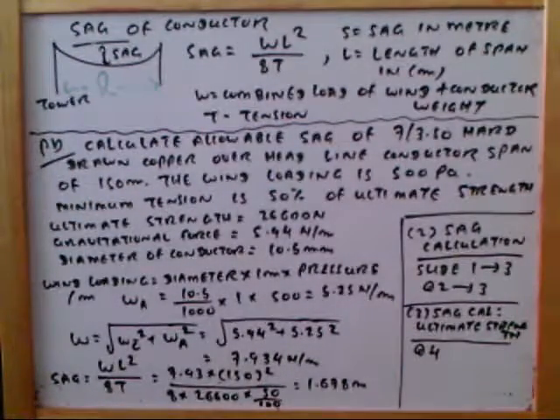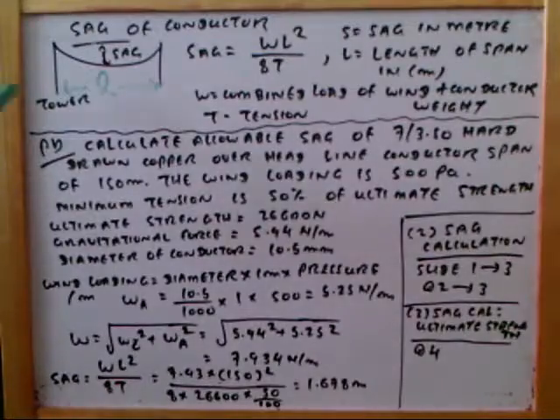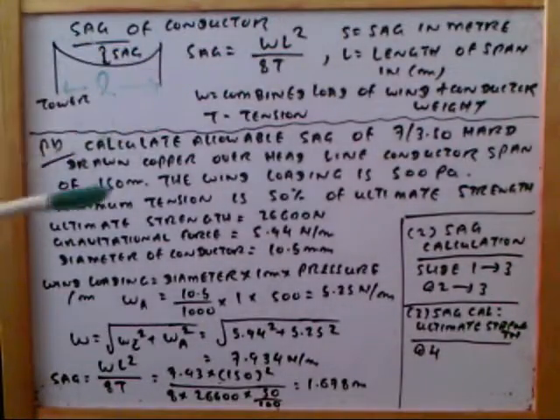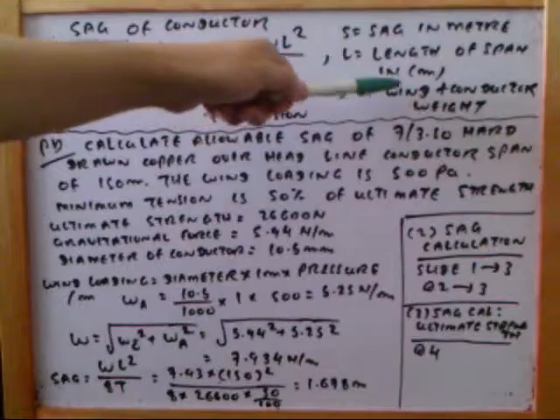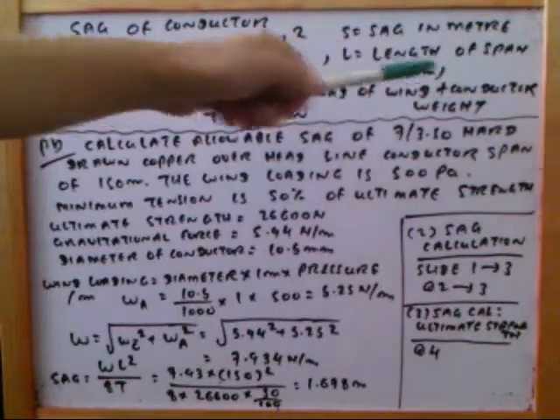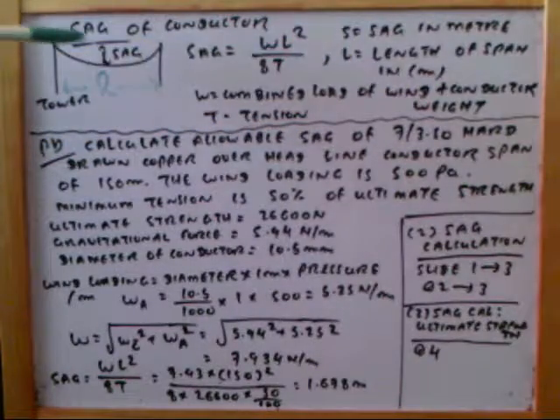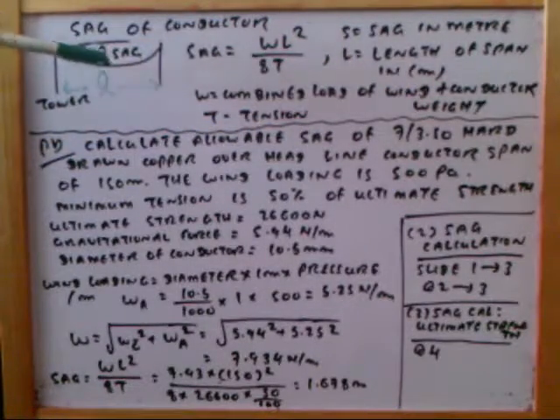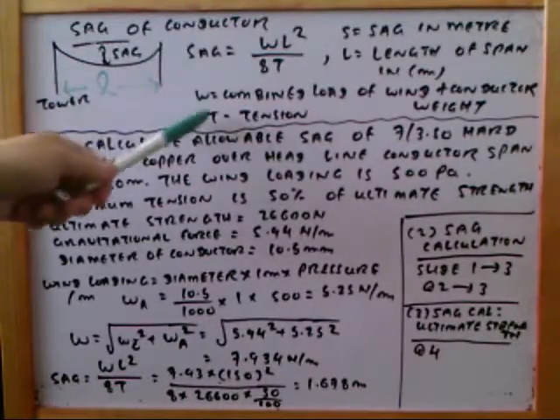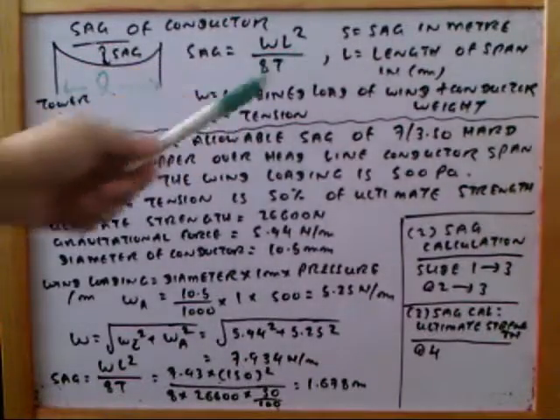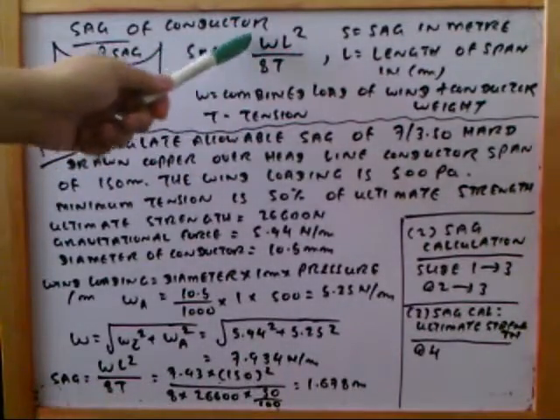So 'L' is the length of the span in meters, and 'w' is the total component load combining the wind load and the conductor weight. Wind load and conductor weight are combined. 'T' is the tension. So sag equals WL² divided by 8T.